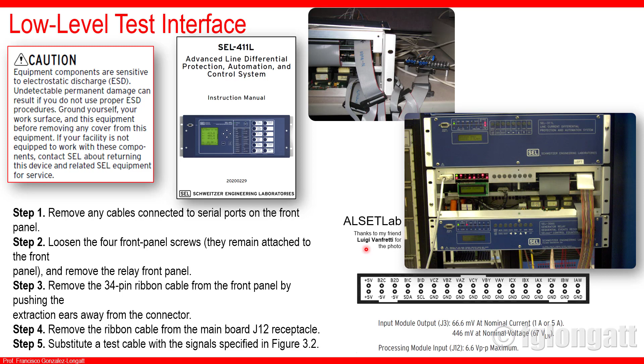As I said before, some relays can be tested using the low level interface. However, you must realize that when doing that, you are not accounting for the dynamic performance of the analog-to-digital converter. For that reason, there are many applications where you cannot use the low level interface. If you are assessing the whole relay as an entire device, you need to apply the appropriate level of voltage and current, and power hardware in the loop is the only solution.